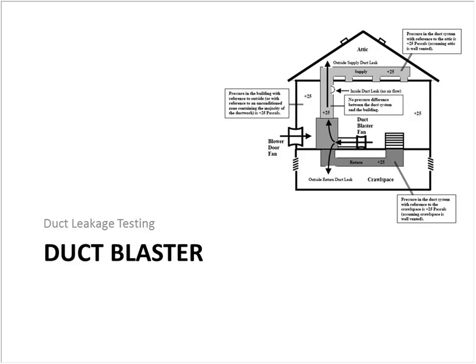The requirement for duct leakage testing totals can be done either during the final testing process, and at that point you would only be testing for total leakage to the outside during the process that I just described, and you would be allowed 4 CFM of leakage for every 100 square feet of floor space. So we count floor spaces from all conditioned spaces, even though it may not be considered a floor space based on the sales appraisal. So we do count conditioned space in the basement. And if it's a 3-story, you've got a 1,000 square foot footprint, then it would be 3,000 square feet. A 3,000 square foot home would be allowed, let's see, that would be 120 CFM of leakage to the outdoors.